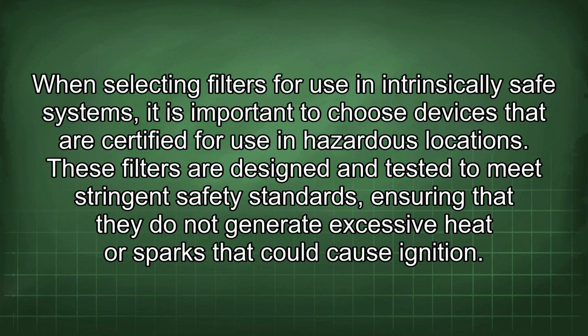When selecting filters for use in intrinsically safe systems, it is important to choose devices that are certified for use in hazardous locations. These filters are designed and tested to meet stringent safety standards, ensuring that they do not generate excessive heat or sparks that could cause ignition.